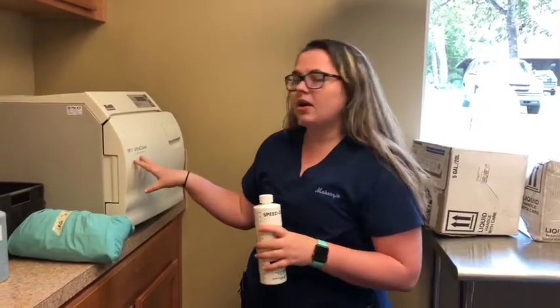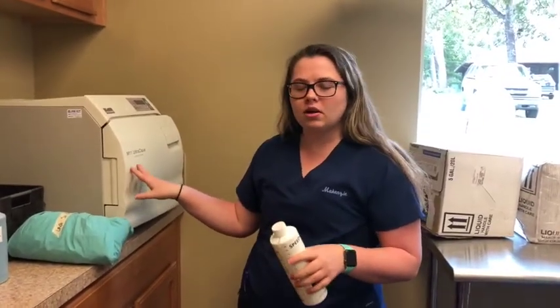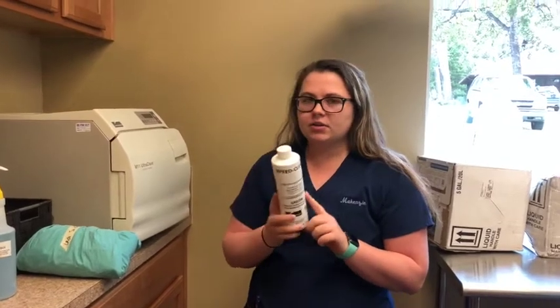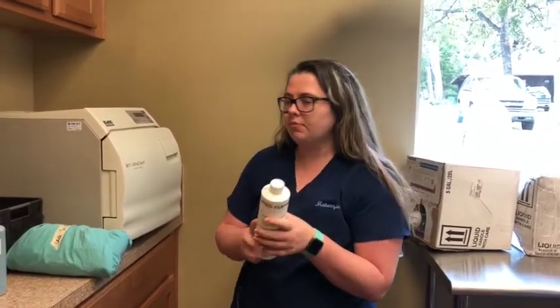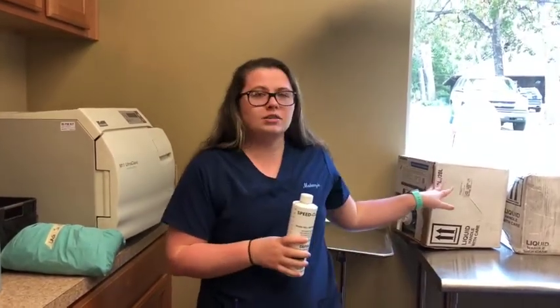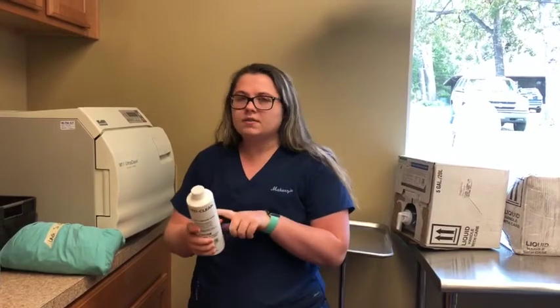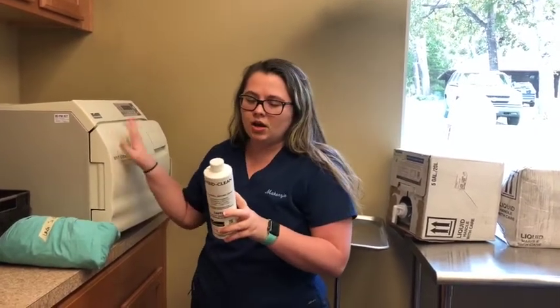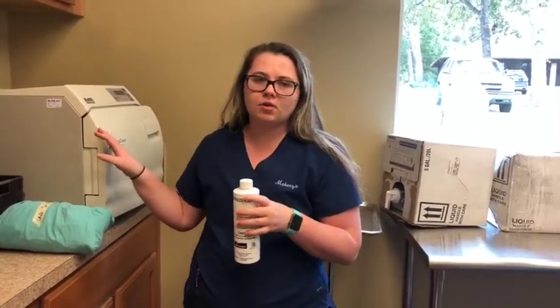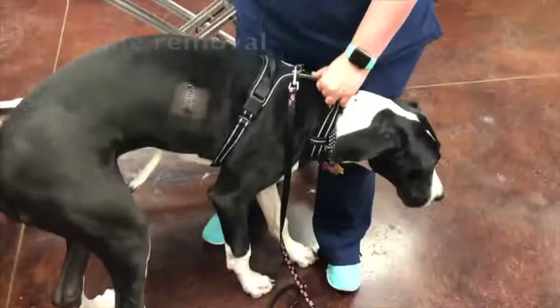So today we're going to talk about how to do our monthly maintenance on our autoclave. So we have this speed clean that we will use, and basically you want to make sure you have no packs or anything inside the autoclave. You will drain it and then refill it with our demineralized water, and then you put an ounce of the speed clean into the autoclave, and then you'll run a cycle, and then each time you'll drain and then refill the water, and you'll run that cycle 3 times for our monthly maintenance on our autoclave.